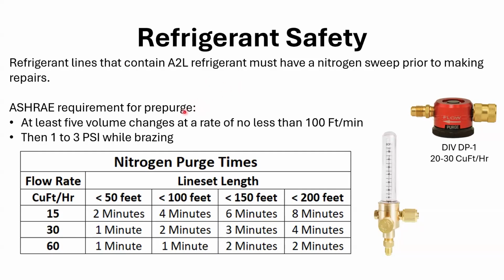So the ASHRAE requirements for pre-purge: at least 5 volume changes at a rate of no less than 100 feet a minute, then 1 to 3 PSI while brazing. So do that purge sweep, get a good rate, right? And that's what this chart is showing down here, cubic feet per hour based on your footage. So that's where these gauges are nice, right?